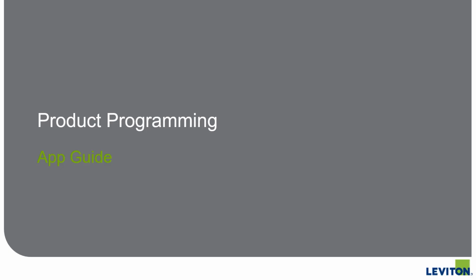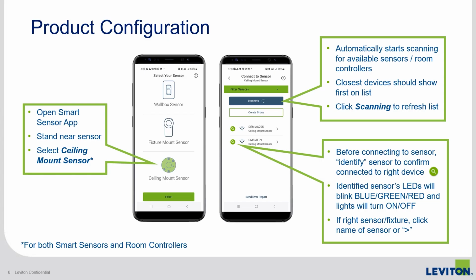Now that we've covered some basics, let's go to product programming. First off, you'll need to open the app on your smartphone or tablet. Click on the ceiling mount sensor icon and press Select. You'll begin to see a list of ceiling mount sensors and/or room controllers in the near vicinity. Generally, the sensors closest to you will appear first or be close to the top of the list. Press the green Identify magnifying glass next to the sensor. The sensor will begin to blink with multicolored LEDs and the light that it's connected to will toggle on and off. If this is the sensor that you'd like to connect to, click on the name of the sensor or the caret to the right.